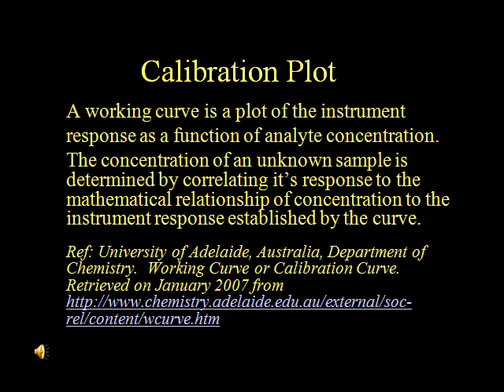In order to determine the acceptable calibration, we look at the working curve, which is a plot of the instrument response as a function of analyte concentration. The concentration of an unknown sample is determined by correlating its response to the mathematical relationship of concentration to the instrument response established by the curve.